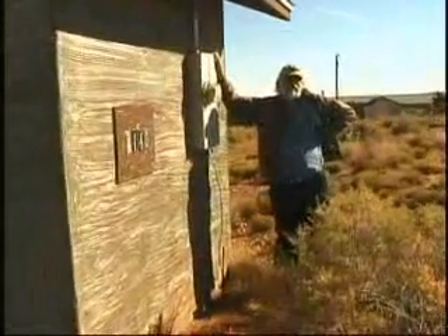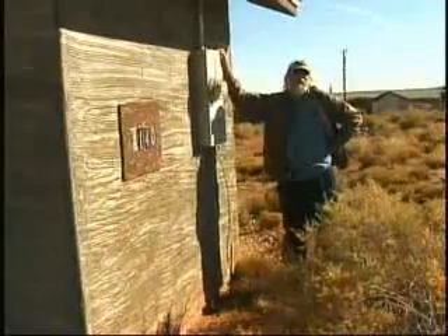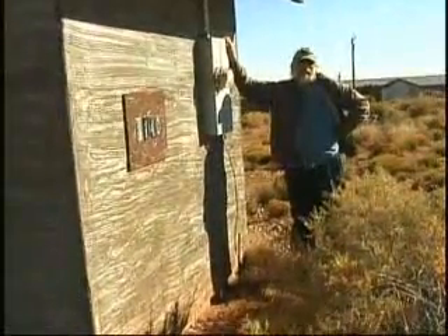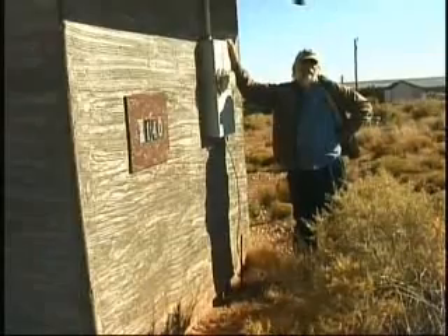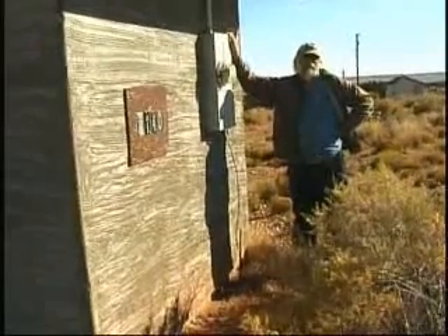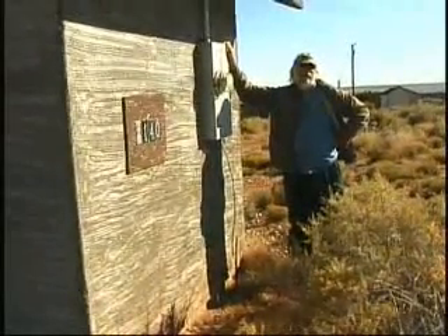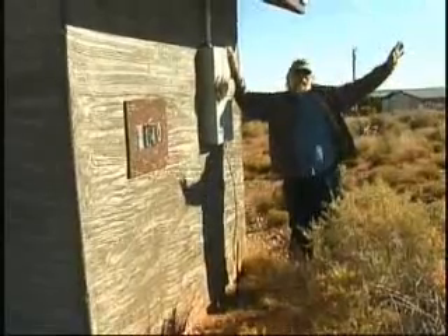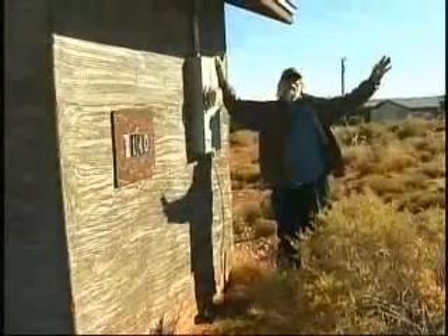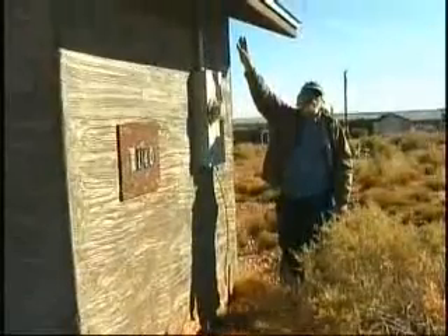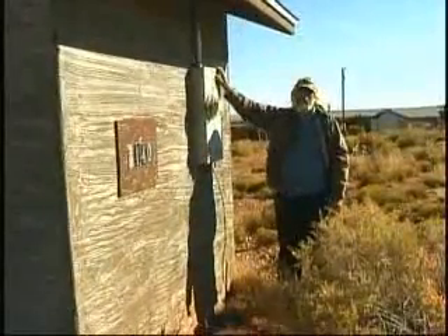This configuration is pretty much the worst case setup for a long wave EMP pulse that would come down the main electrical wires. It would enter right at the roof of your building and go straight into your panel.